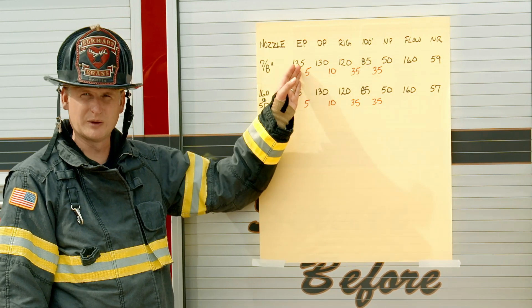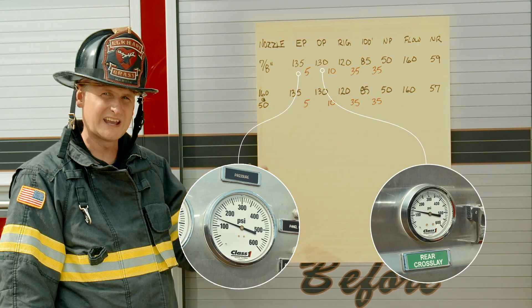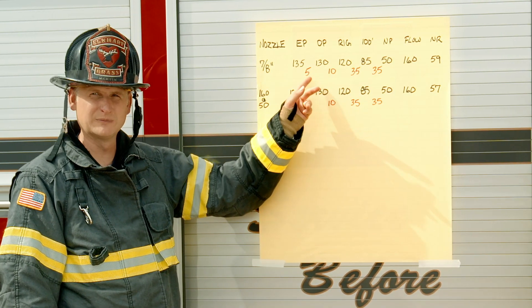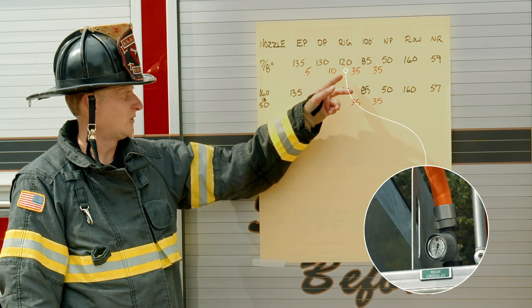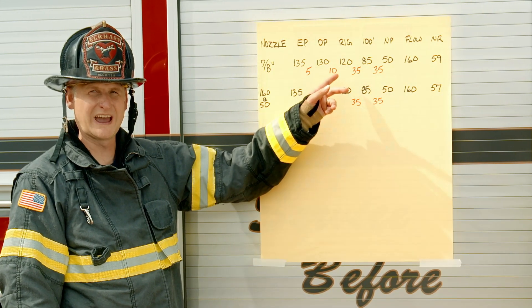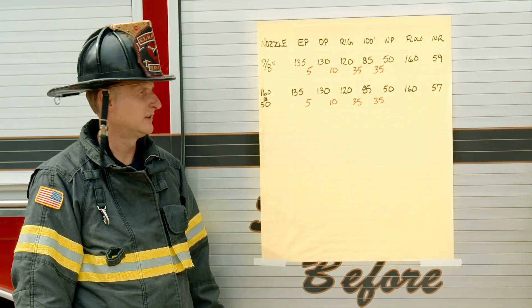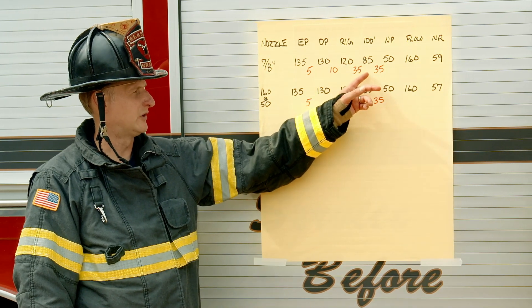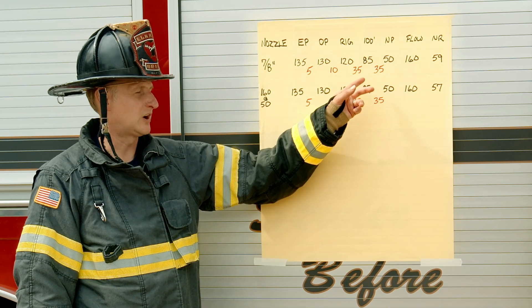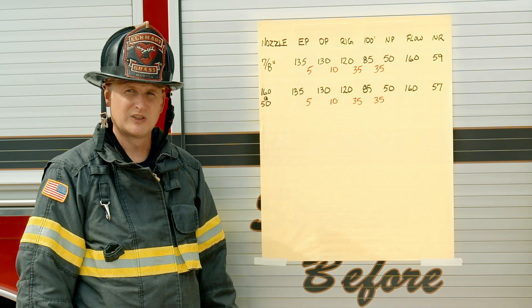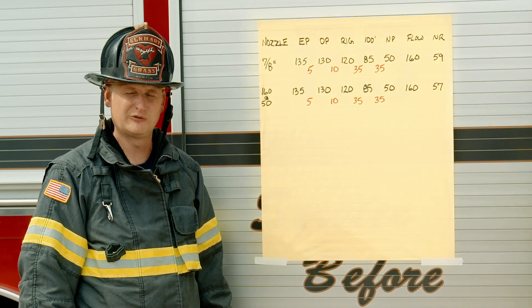Let's pay attention to the plumbing for a minute. The big gauge was 135 and the little gauge was 130. You could take a different colored marker and write the difference between those two to make it obvious. The rig is where it came off with a swivel, so if I were looking at the big gauge when pumping, I would be losing 15 PSI just in my plumbing. The difference between the rig and the first 100-foot mark is 35 PSI, and the 100-foot mark to the nozzle pressure was also 35 PSI. That tells me the friction loss per 100 feet of this particular attack hose is 35 PSI per 100 feet.